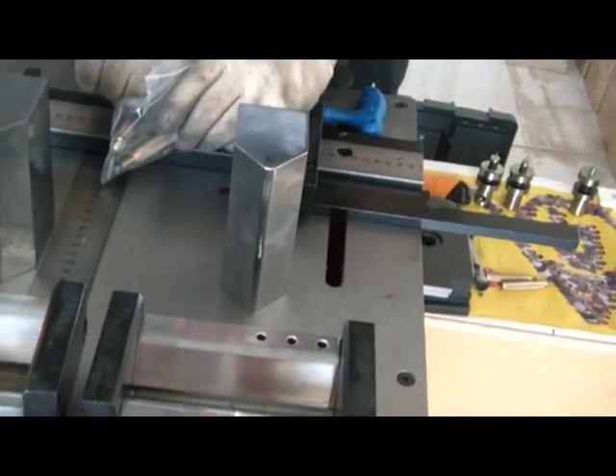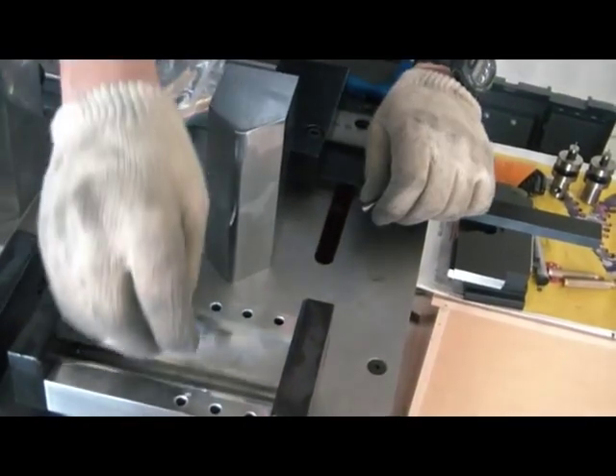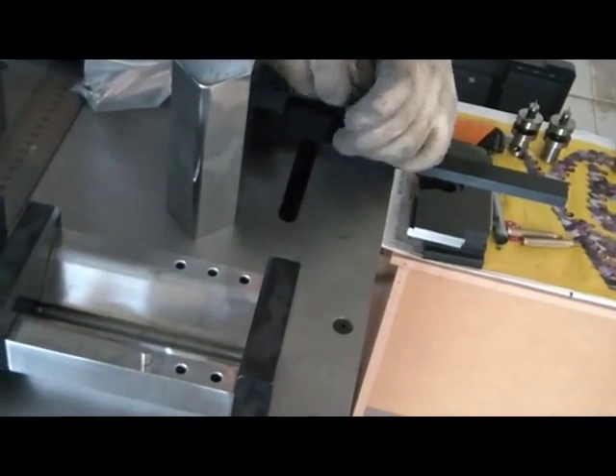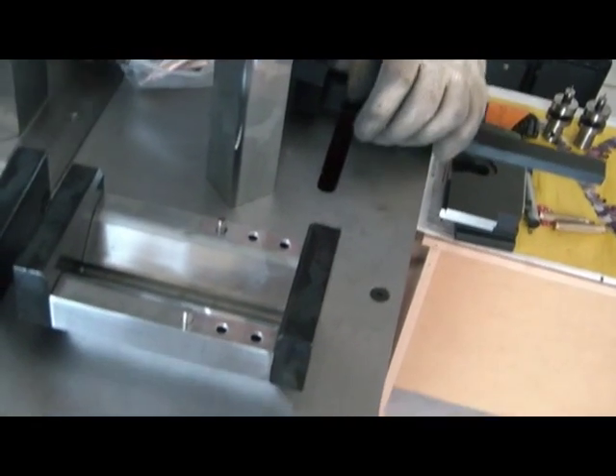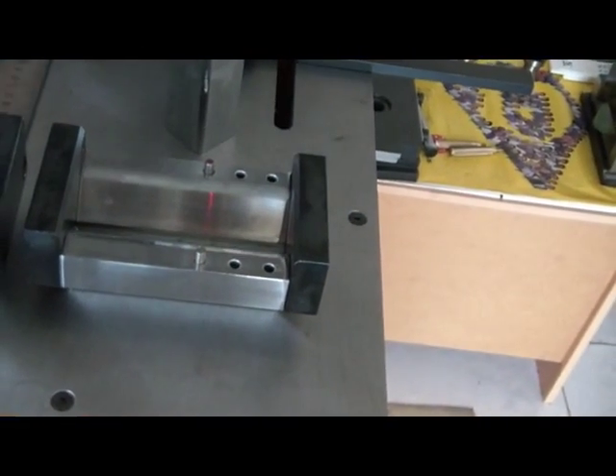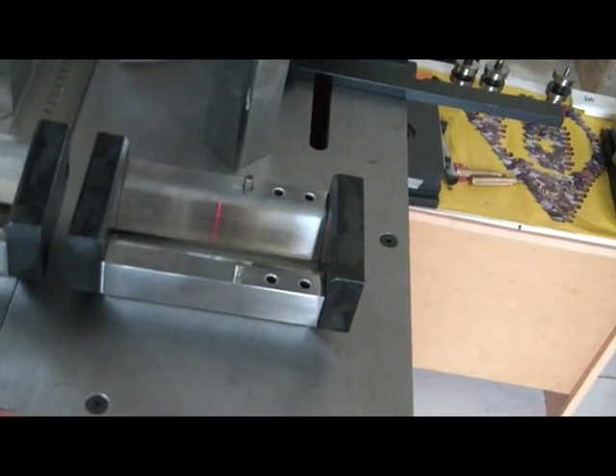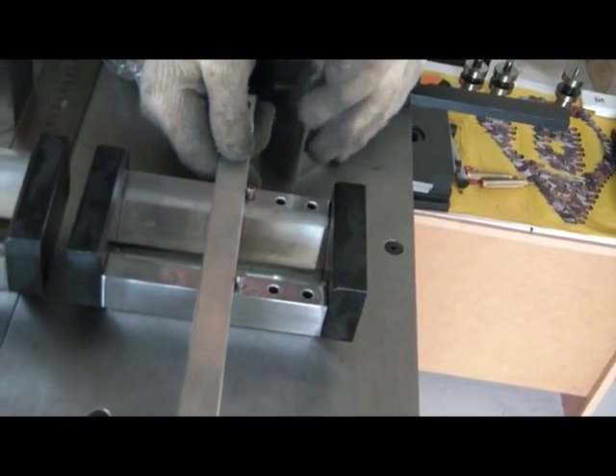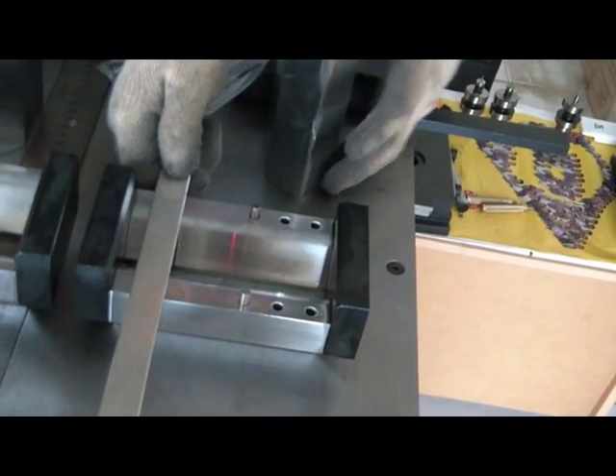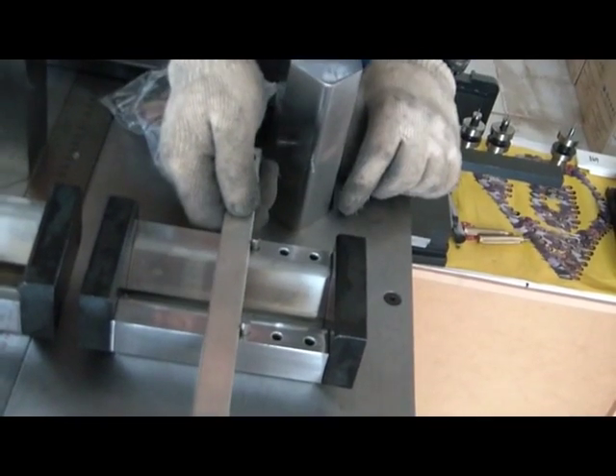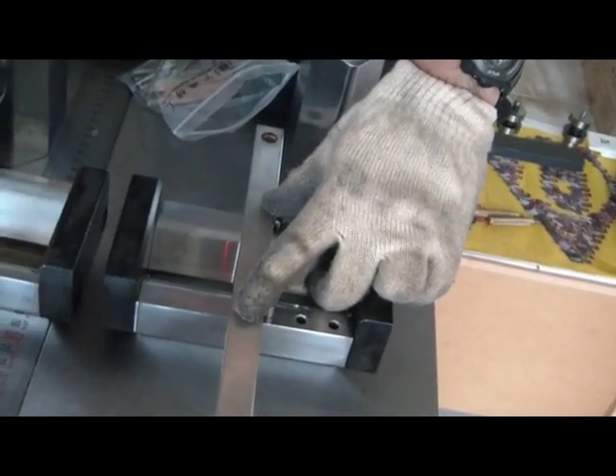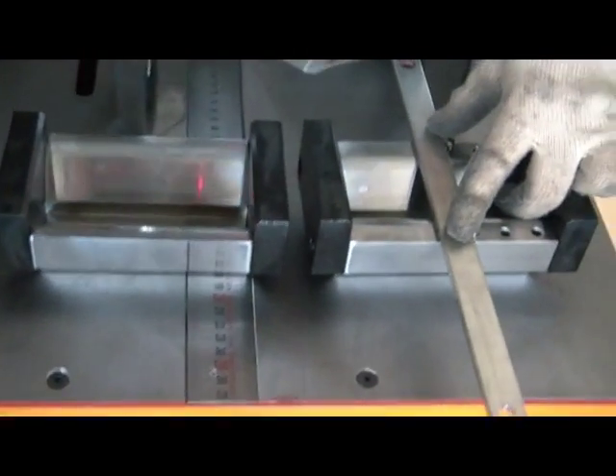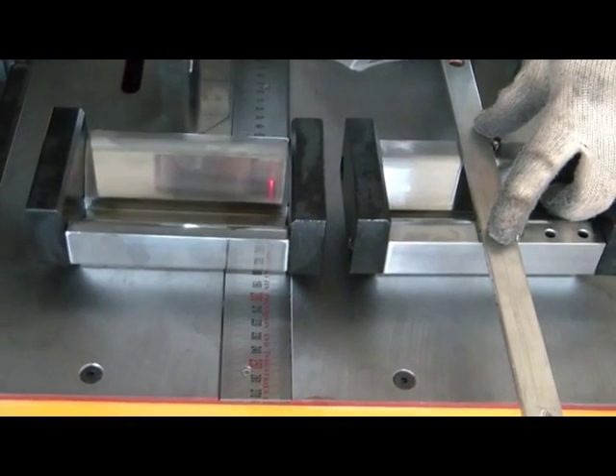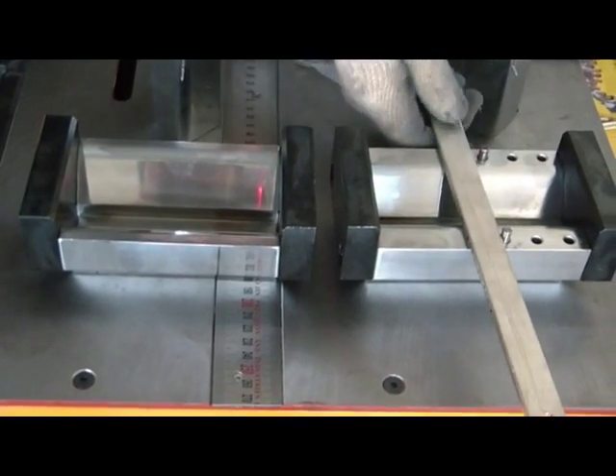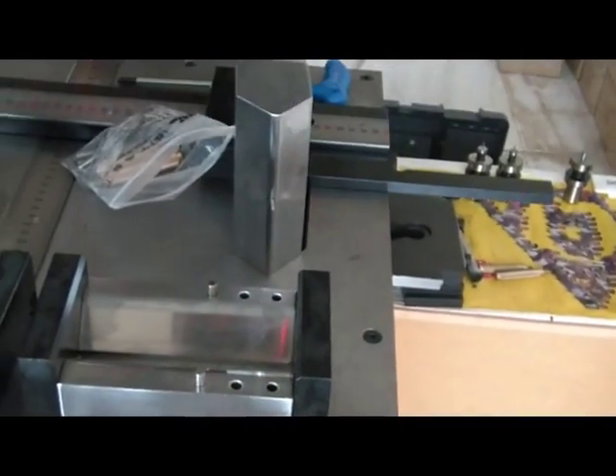This mold, especially for the minimum bus bar, has a guiding pin to bend from the center of the bus bar, because the bus bar must be applied at the center during bending. If it's not centered, the pressure will come off-center, so it must be centered - that's why we are fixing this one. Another one needs to use a scale, in case you want to use our jig guiding bus bar scale. But usually our customers use this one up to 10mm thickness.